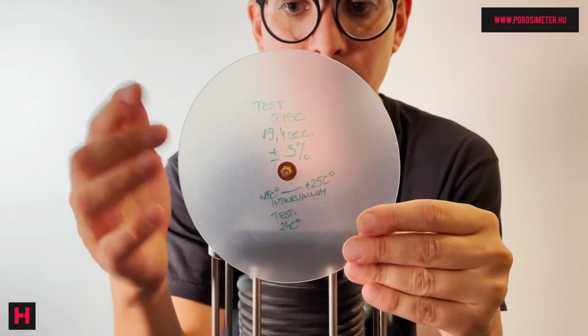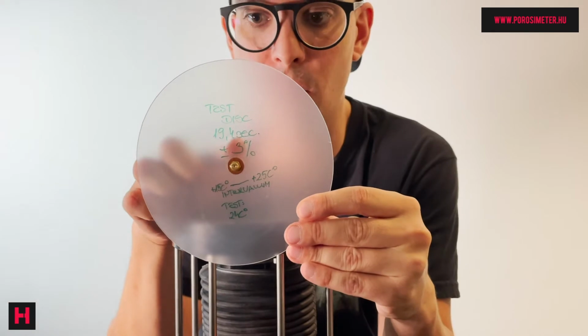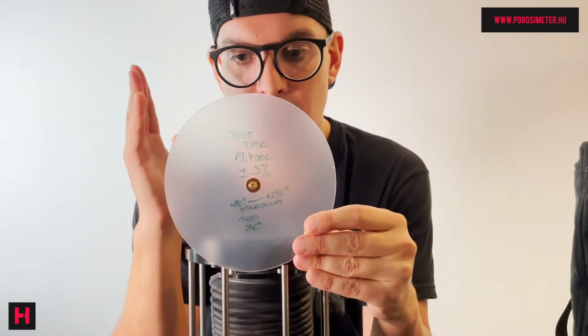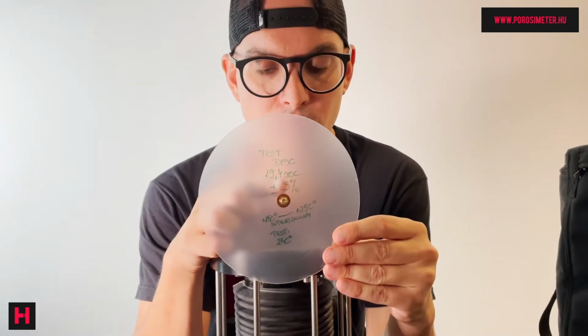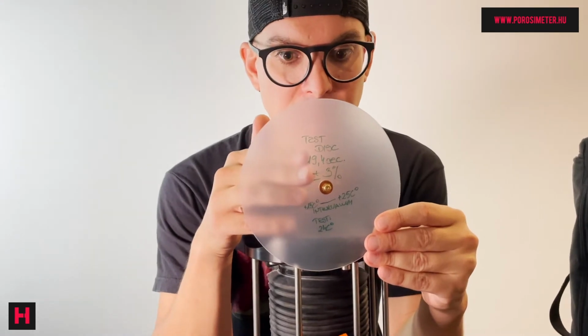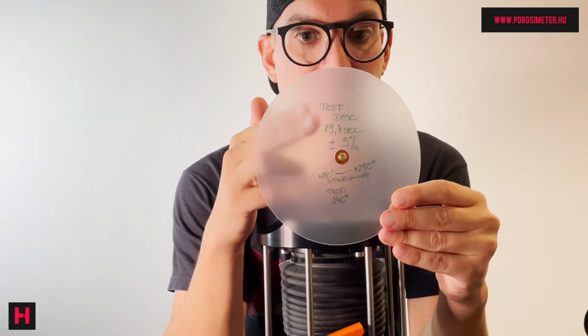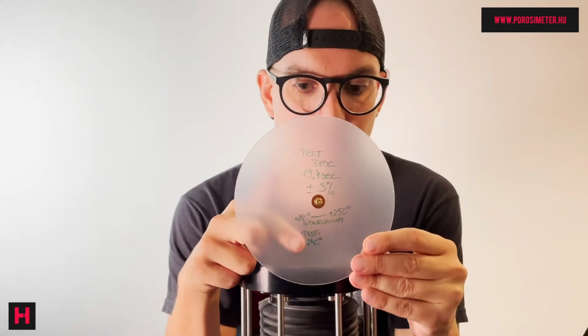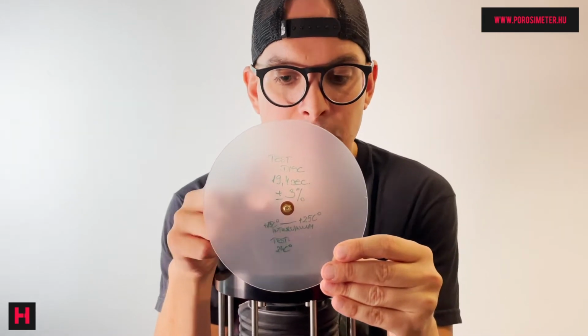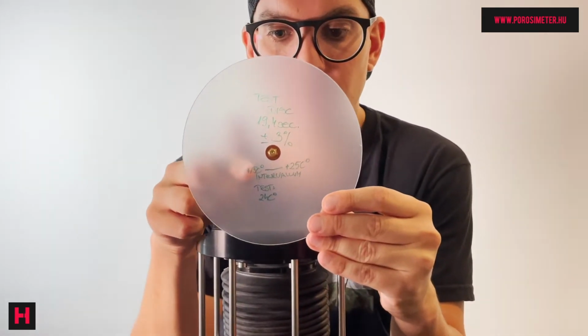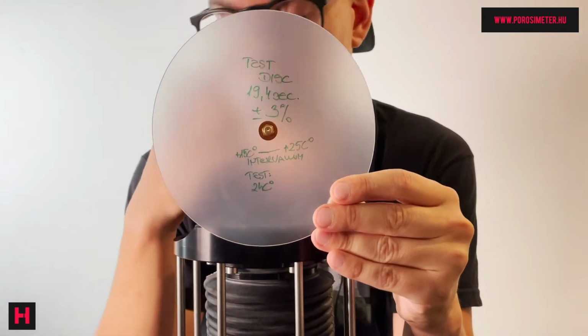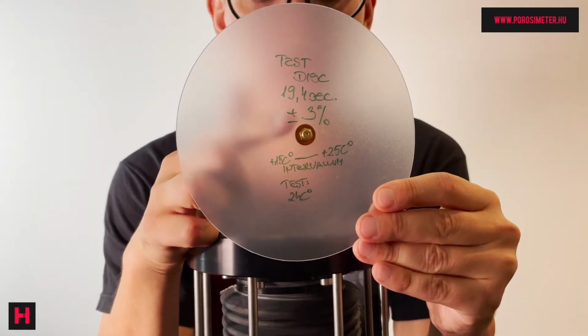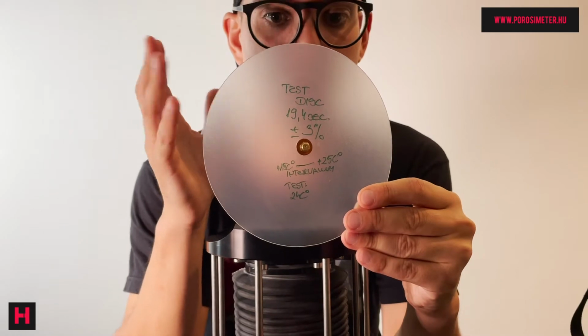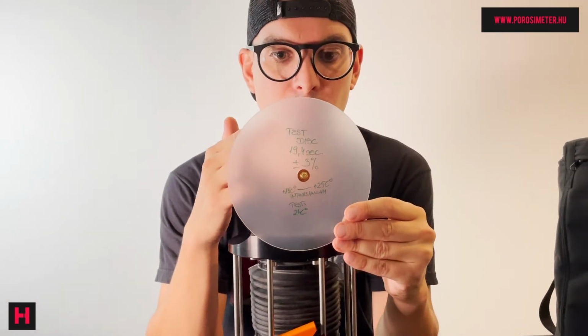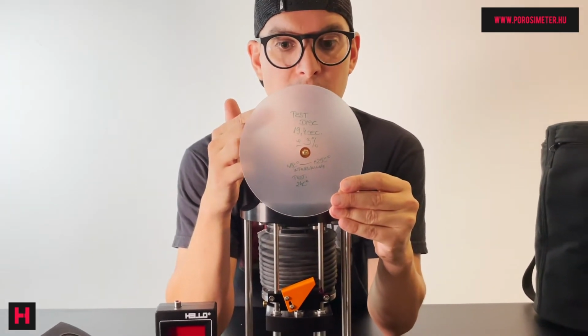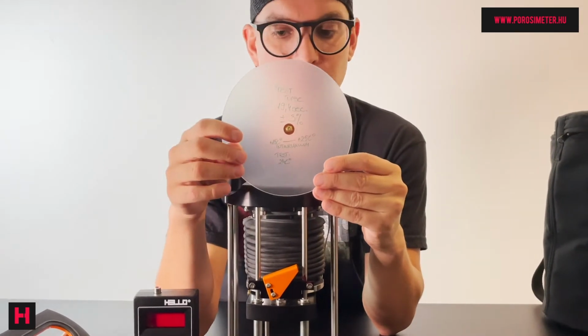Each disc has a number, which especially with this disc is 19.4 seconds, which means when you are doing the accuracy check, the result has to be this 19.4 seconds plus or minus 3%. This is the tolerance. We have this tolerance because we made this accuracy disc at 24 Celsius. You can see it at the bottom, tested at 24 Celsius. And you always need to do the porosity check between 15 and 25 Celsius. That's why we have this tolerance of plus or minus 3%, which in this case is more or less 0.6 seconds. That means if the result is between 20 seconds and 18.8, it's totally perfect. Your Porosimeter is measuring perfectly.